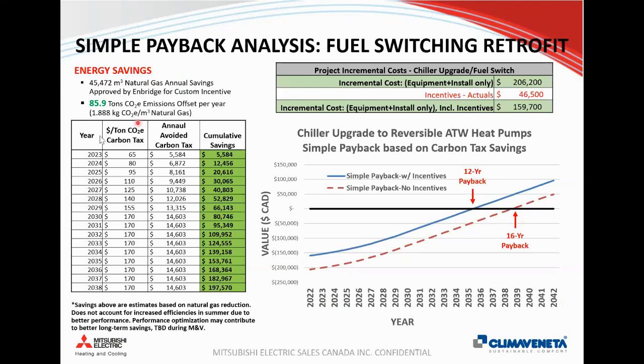So if we look at just the carbon tax and based off 85 tons of CO2 offset per year, in 2023, it's about $5,500, but by 2030, when carbon tax is at $170 per ton, it's about $14,000 savings. But if we look at the cumulative savings, it's $200,000 over a 15-year life cycle. This doesn't include gains of efficiency on the chiller side as well. So replacing a chiller that's 20 years old with today's high efficiency chiller that meets ASHRAE 90.1 will have some good benefits. And also with the current control scheme that we talked about, we're certainly going to look to optimizing that in the future to have the heat pump running for more of the time, because the more of the time the heat pump can run, the more gas we can offset and the more savings that can be realized.